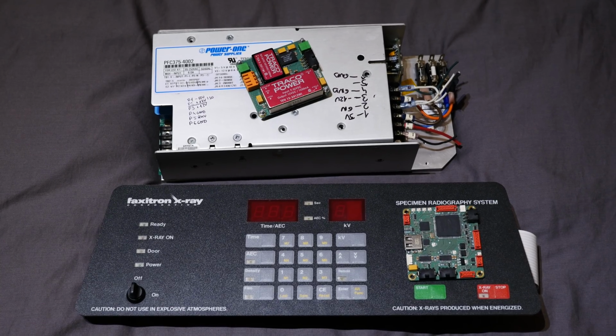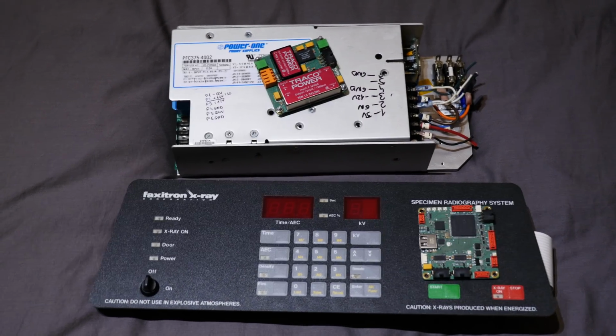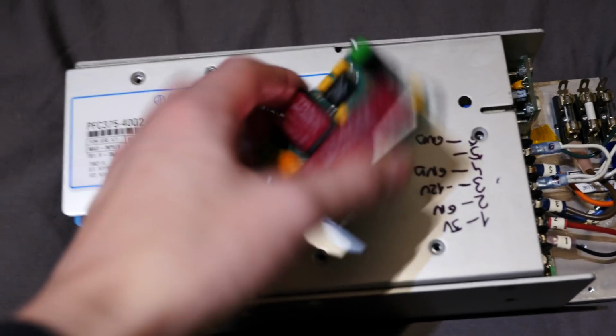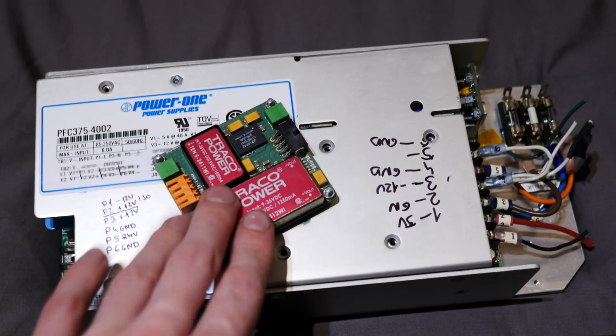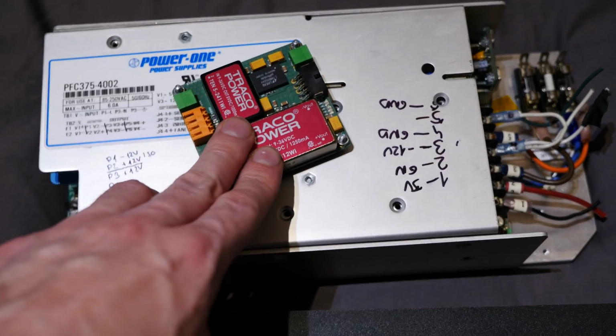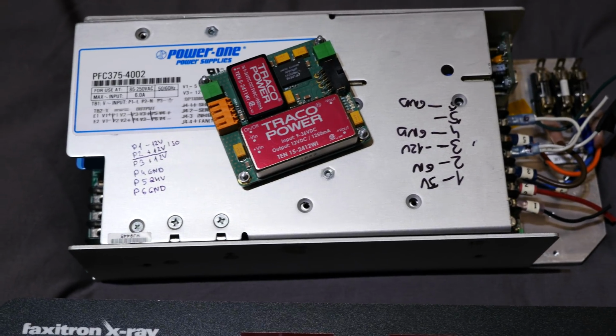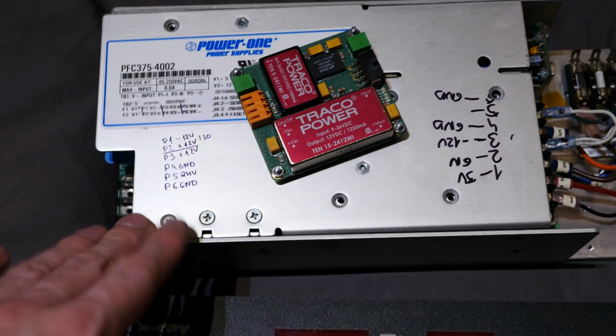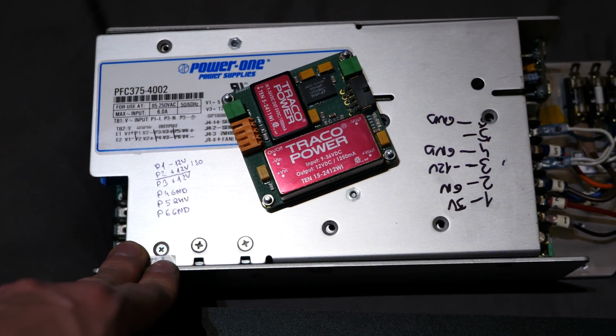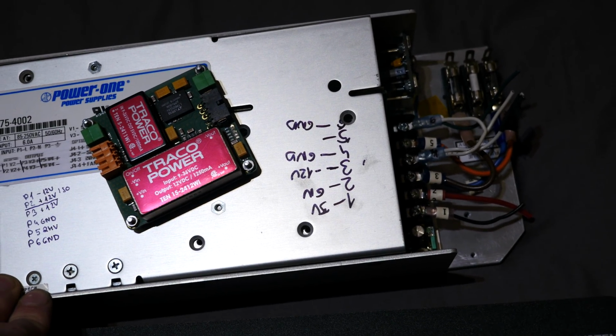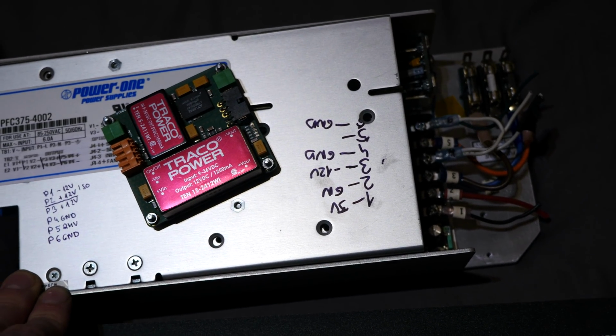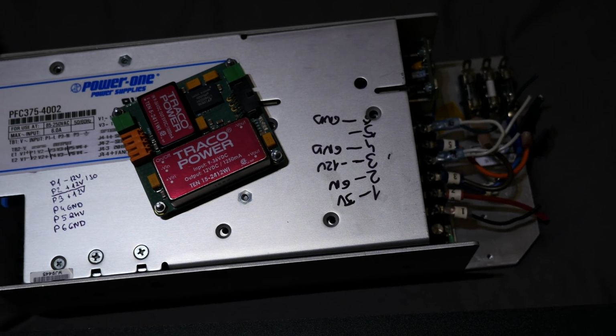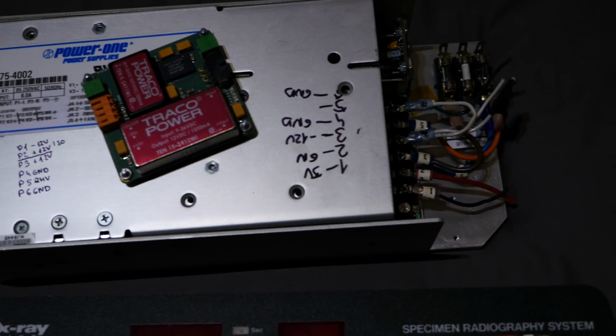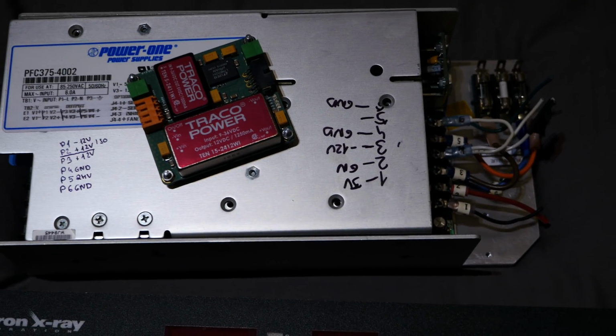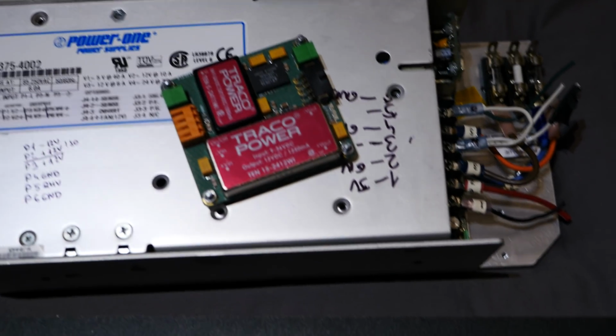Okay, so in this shot you see all the electronics and new electronics. So this is my power supply that I made. It's just enough for this X-ray machine. It's only 20 watts, and Faxitron uses a 500 watt power supply. The supply is so big that you need to load it with a few amps in order to start it. So if you disconnect the sensor, like a Hamamatsu sensor, it won't boot. If you disconnect anything, it won't boot. That's just crazy. So I made a small power supply for this.